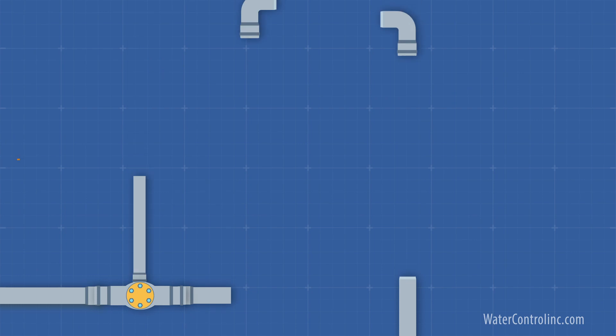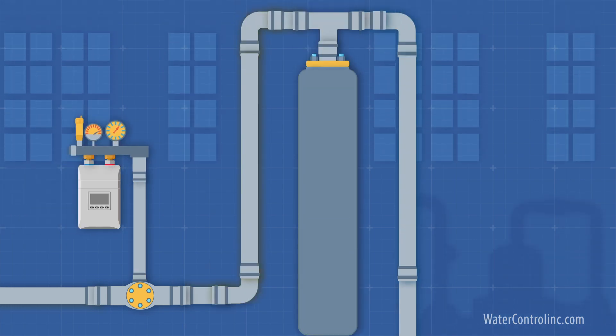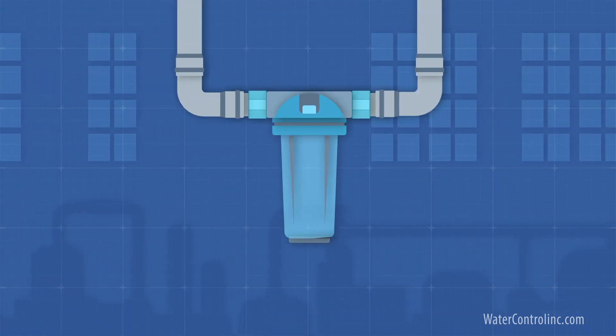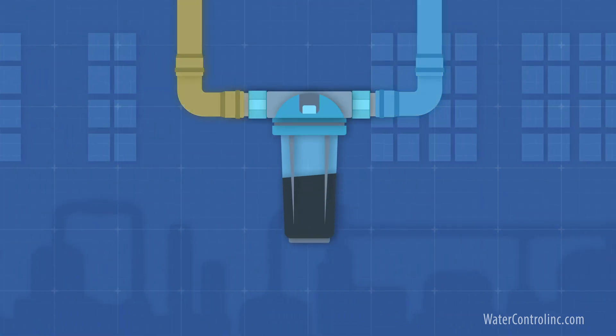Chemical injection systems using chlorine, potassium permanganate, hydrogen peroxide, or even ozone will have a similar effect, and the sulfur can be filtered out via mechanical filtration. A carbon filter is also capable of filtering out lower levels of hydrogen sulfide gas. The media absorbs the gas and eventually must be replaced. Different means of aerating that carbon media can aid in oxidizing the hydrogen sulfide so it can be backwashed out and that media life can actually be extended.